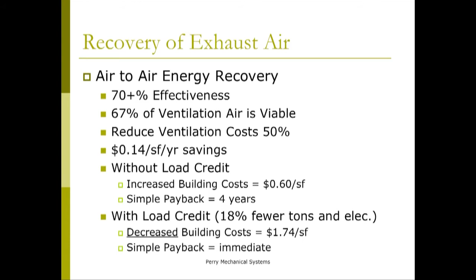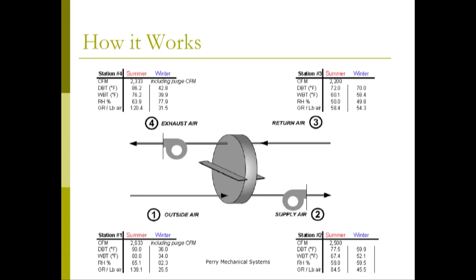This shows a diagram of how it works. You bring return air from your building through one side of a wheel-type heat exchanger and exhaust it out, while bringing outside air through the other side of the wheel. It cools down because the heat from the exhaust air is transferring over to the incoming air. There are different kinds of heat energy recovery, and in our environment the only one that really makes sense is true energy recovery, or enthalpy recovery, because you want to recover the latent load as well as the sensible load - meaning the humidity as well as just the heat. Not all technologies that transfer heat allow that, so typically for this type of system you'll be using a wheel.